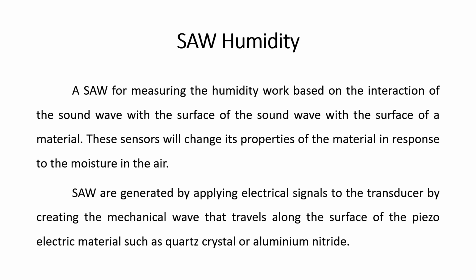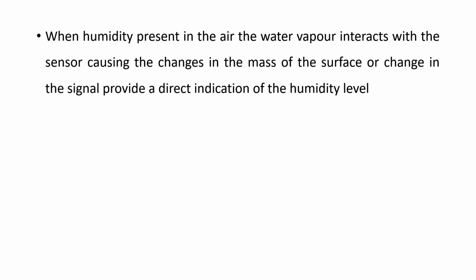SAW humidity. A SAW sensor for measuring humidity works based on the interaction of the sound wave with the surface of the material. These sensors change the properties of the material in response to the moisture in the air. SAWs are generated by applying electrical signals to the transducer, creating a mechanical wave that travels along the surface of a piezoelectric material such as quartz crystal or aluminum nitride. When humidity is present in the air, the water vapor interacts with the sensor, causing changes in the mass of the surface. The change in the signal provides a direct indication of the humidity level.